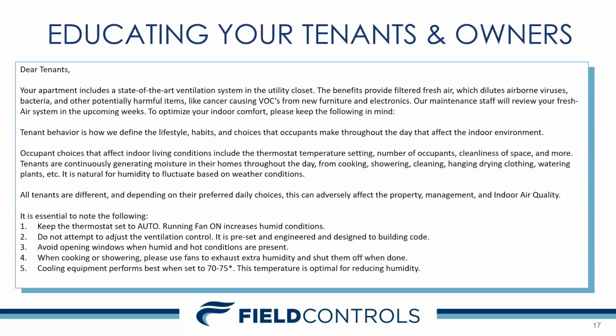If you run any type of fan, it's going to pull air in these types of envelopes. And that contributes to not optimal air, especially when you're providing overventilation. The cooling equipment performs best when set to 70 to 75 degrees. The temperature is optimal for reducing humidity. In the case where we found out and did our analysis, the temperature was set to 80 degrees, which meant no cooling was happening, and thus we were not able to reduce any of the load for moisture.